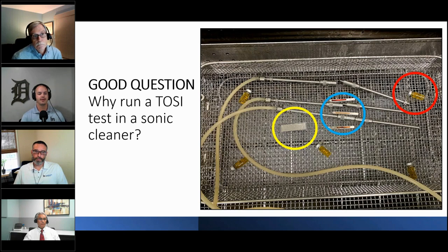surfaces of instruments. Now, you may have noticed that the contents there in that blue circle is our test for internal surface cleaning ability. So those coupons that are sitting out are normally, throughout the test cycle, inside those stainless steel cannulas that you see there. And hopefully you can tell pretty easily that the soil is still there. So in this particular case, the lumen flushing and cleaning function of the ultrasonic was not working. And I can tell you, because we ran this test and we looked into what was causing the problem, we found out that the tubing that was supplying all of the flow to those lumens was being kinked when the lid came down on the ultrasonic when we started the cycle.